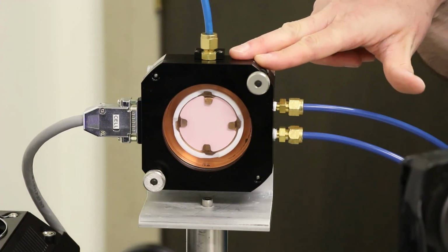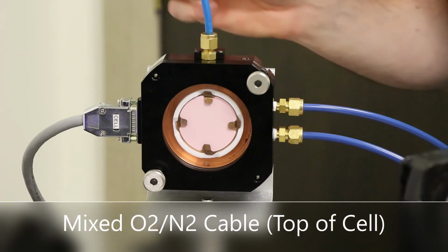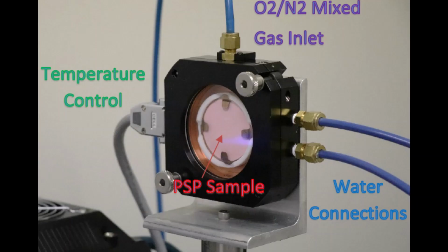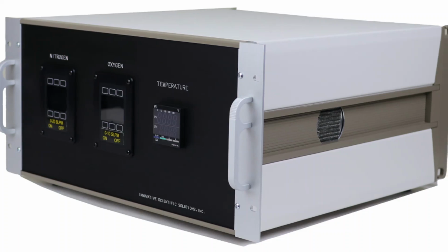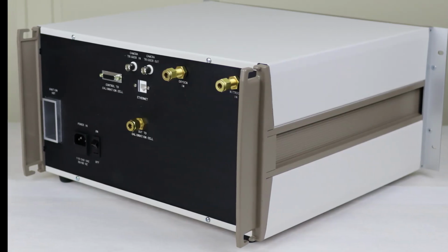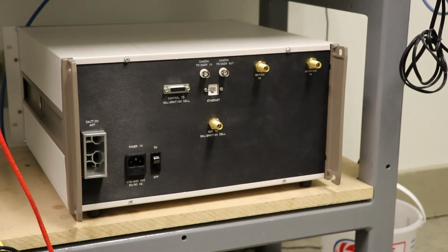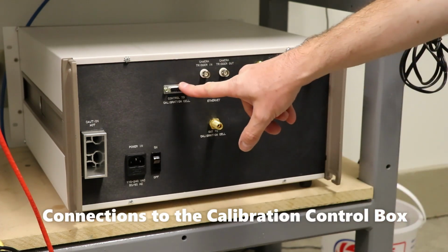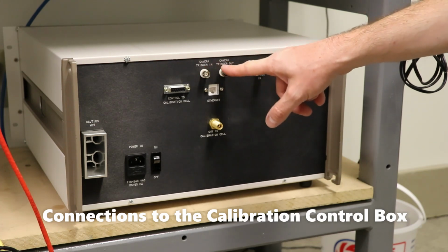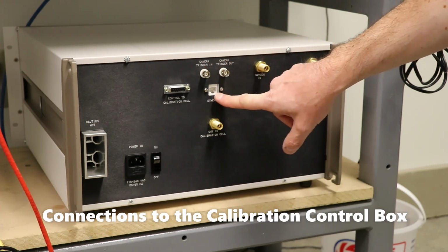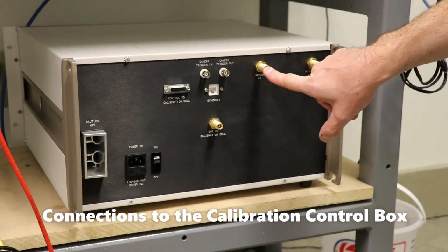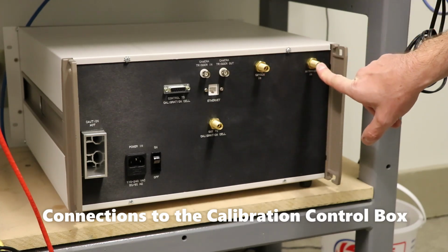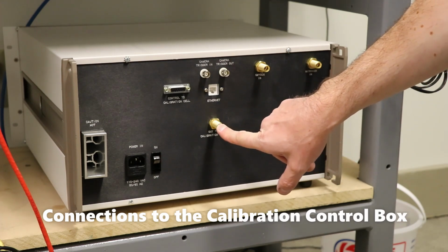Three cables connect to the cell itself. There are two water supply cables and one mixed gas supply cable. On the back of the calibration system, there are connections for the temperature controller, the input and output trigger from the camera, Ethernet connections for communication, oxygen input to the system, nitrogen input to the system, and mixed oxygen and nitrogen out to the calibration cell.